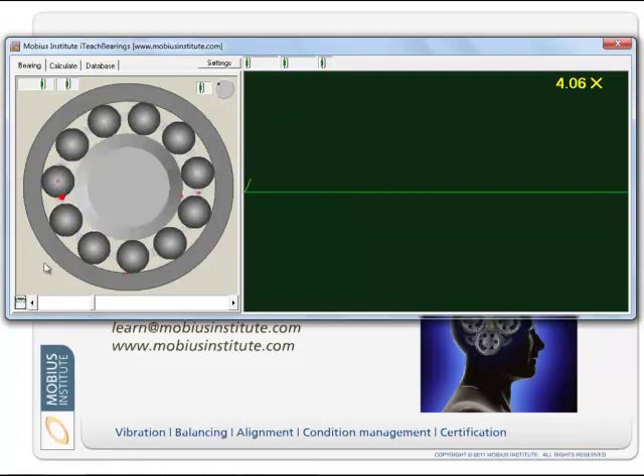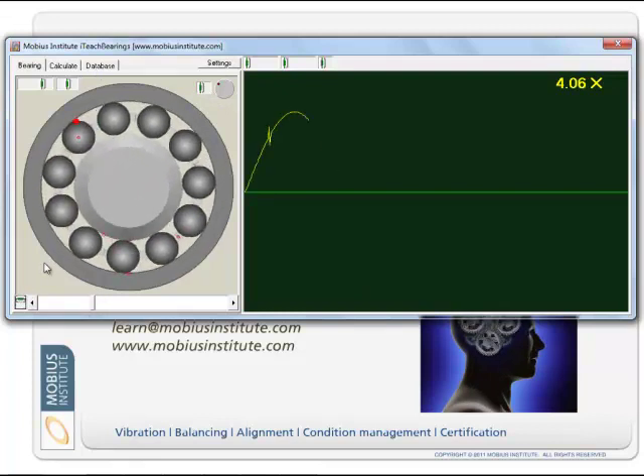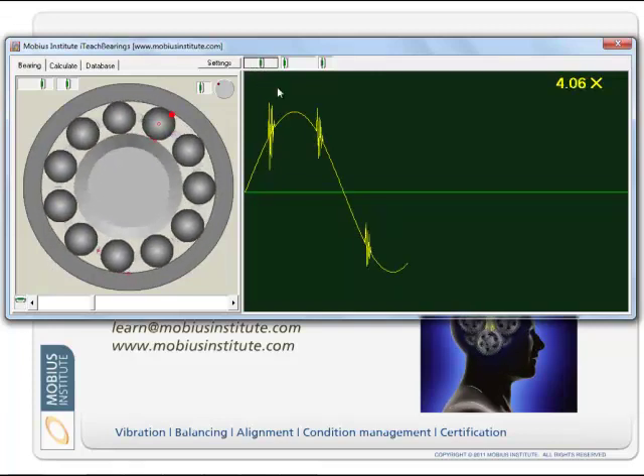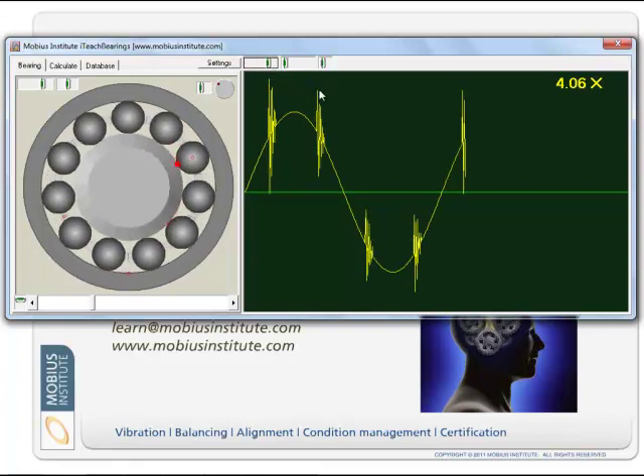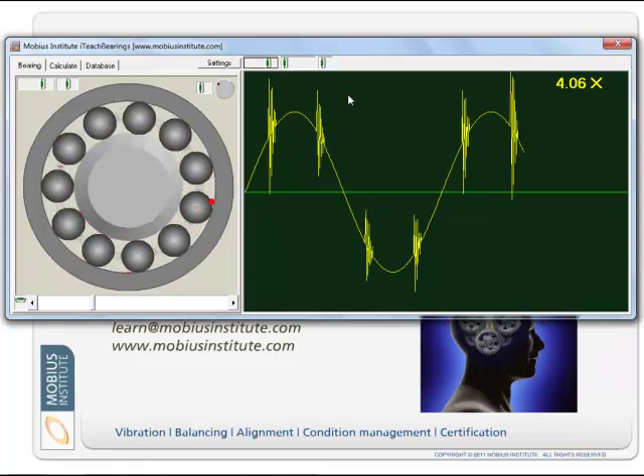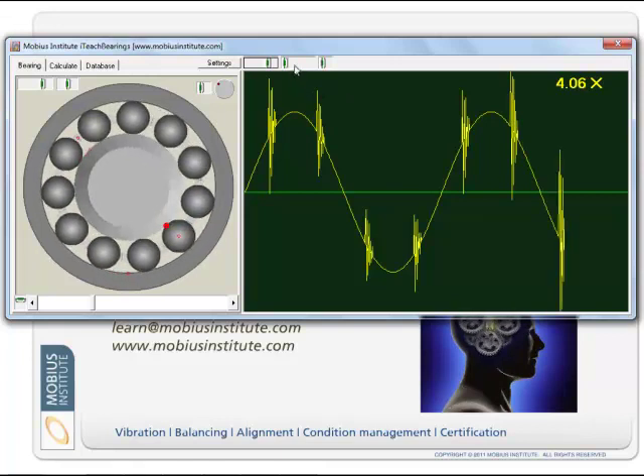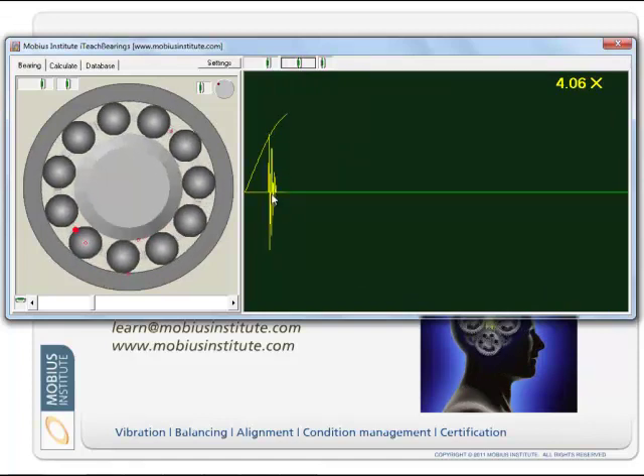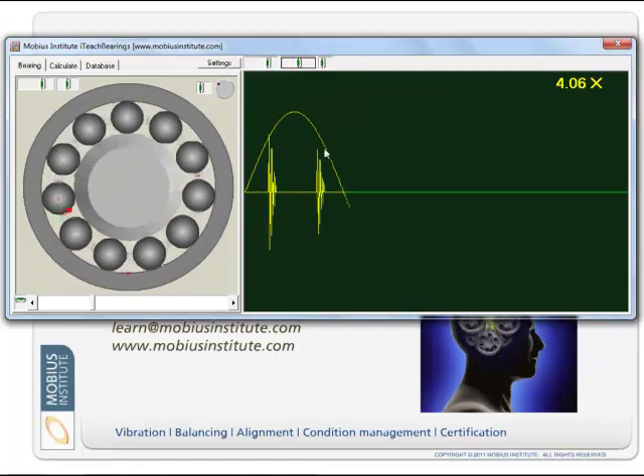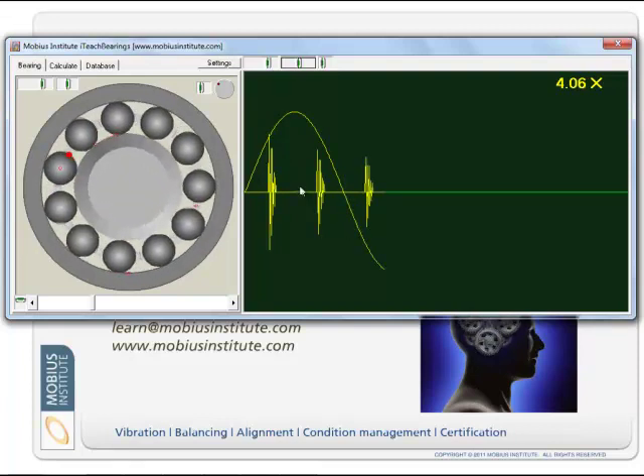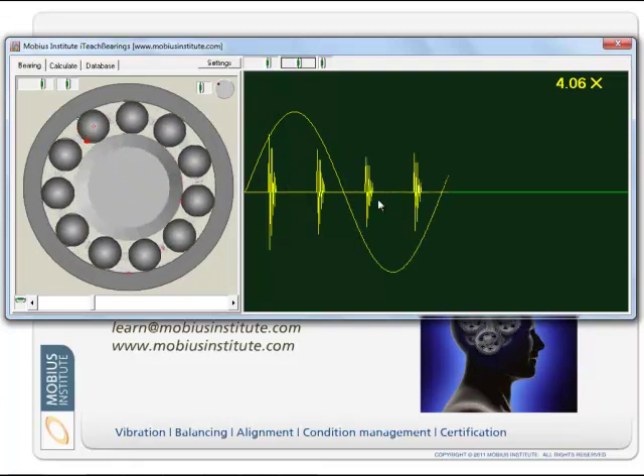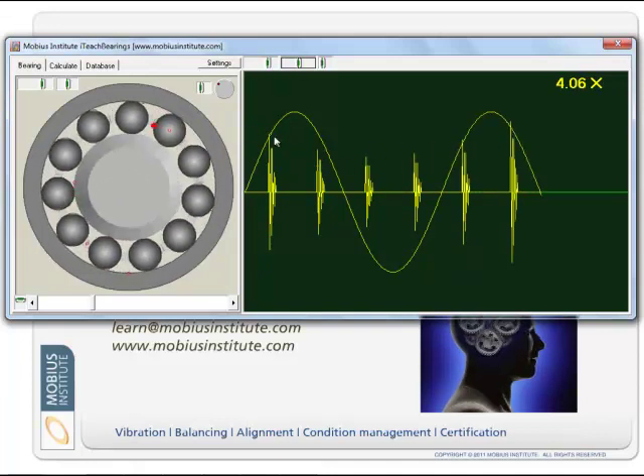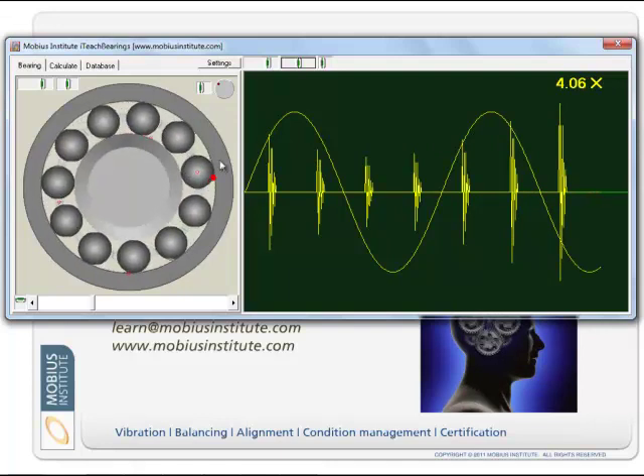Now, what are all the things we can do? We can turn on the bearing and I can come through here and make the fault a bit worse and a bit worse, and just look at how the vibration might change. Now, of course, this is all exaggerated — you can see these faults. But something I can do is say, what if we put it through a filtering process such that now we just get the defect. You can still see the once-per-revolution vibration here, but now we see these defects and you can see how the vibration is changing.